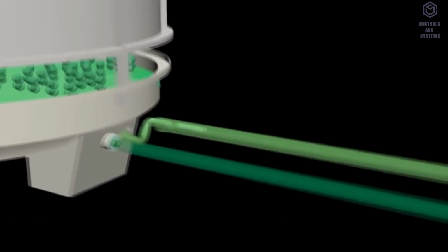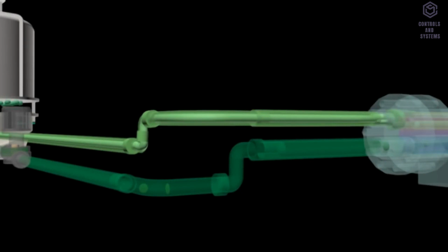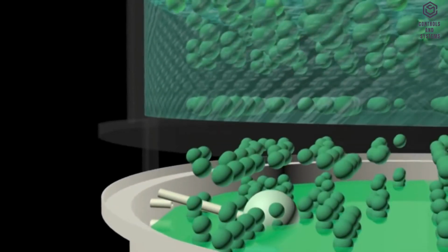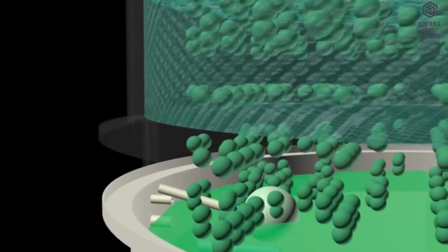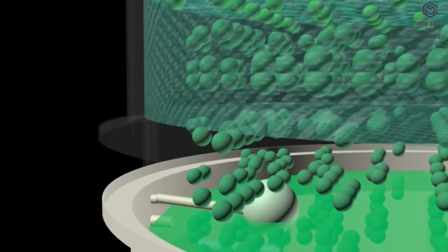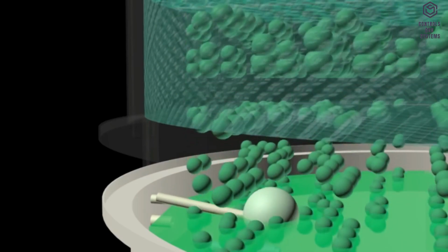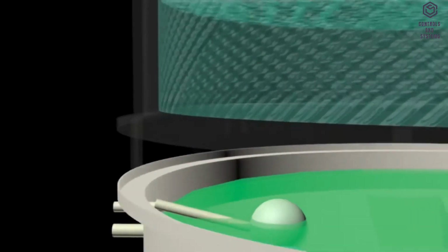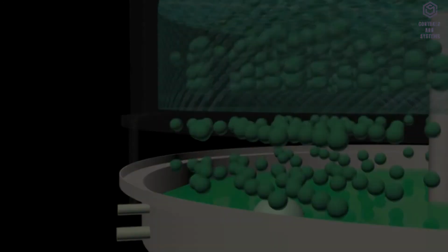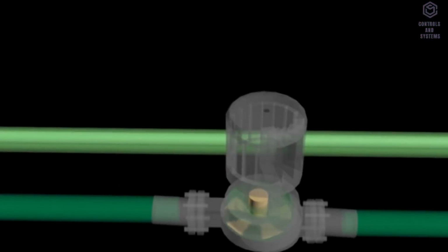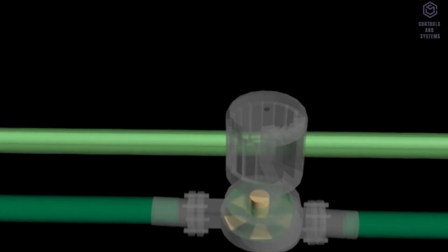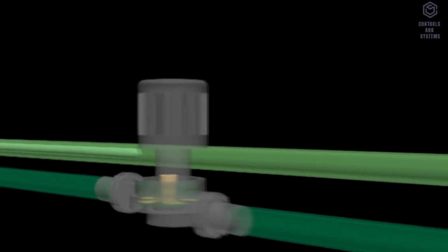This condenser water will flow back to the chiller to continue the heat absorbing work from the refrigerant. The basin at the water base is connected to the makeup water tank. It works for adding water when the water level in the basin decreases to a certain level due to evaporation. This condenser water cycle will continue as long as the centrifugal pump is in good working condition.